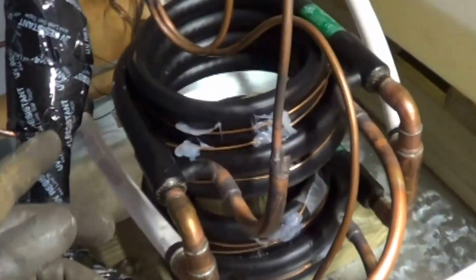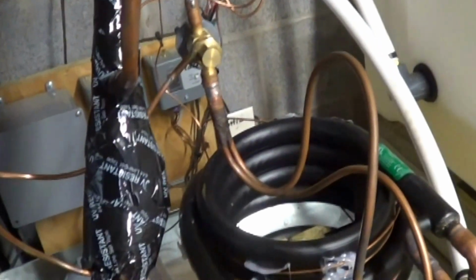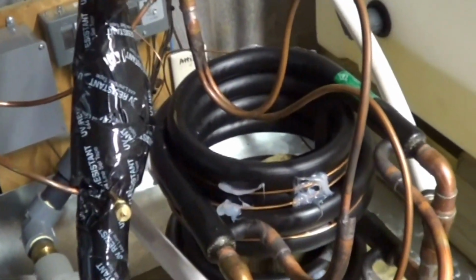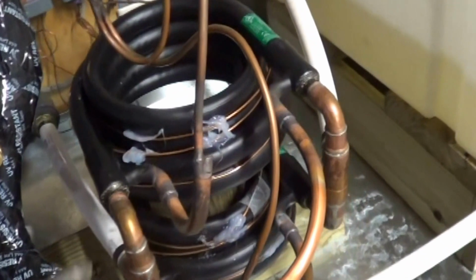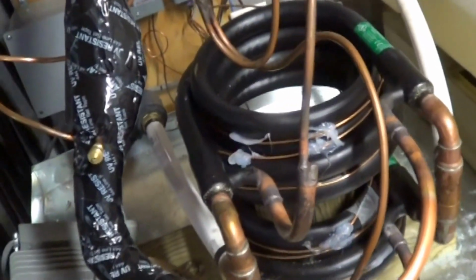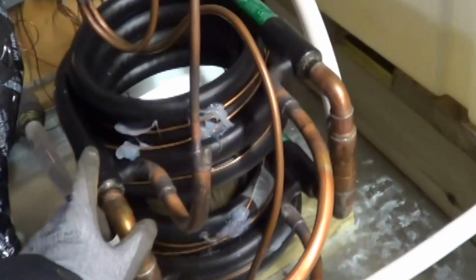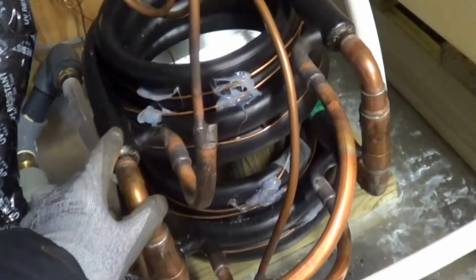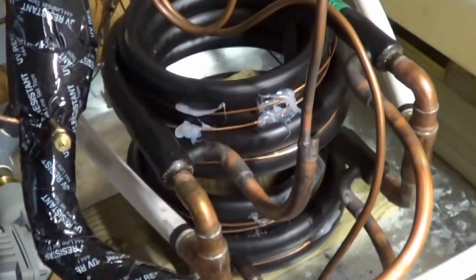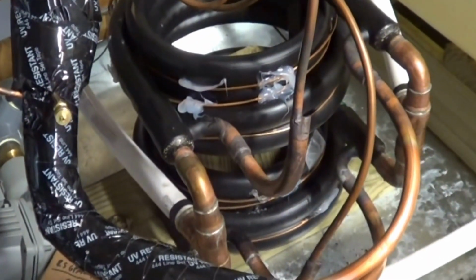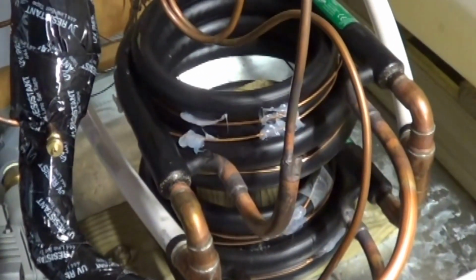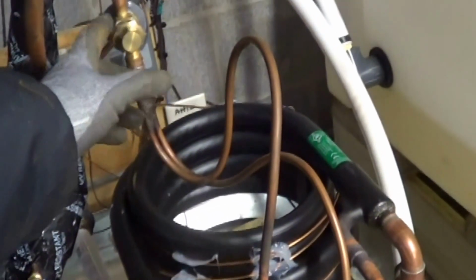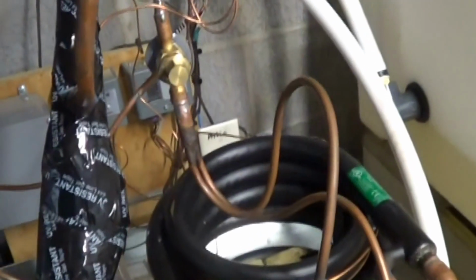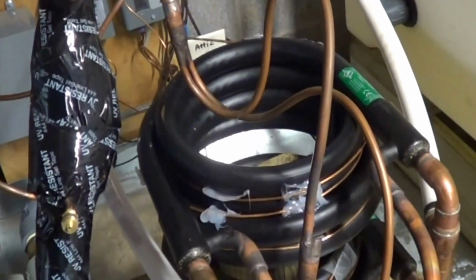And highly recommend fixed orifice, which is what the Goodman defaulted as. Some units though have expansion valve outside. You're gonna have a hard time because you're not gonna be able to hold the refrigerant in these water coils because they're so much smaller in volume. I definitely recommend an orifice. Expansion valve is fine for the coil itself because the condenser is much bigger.